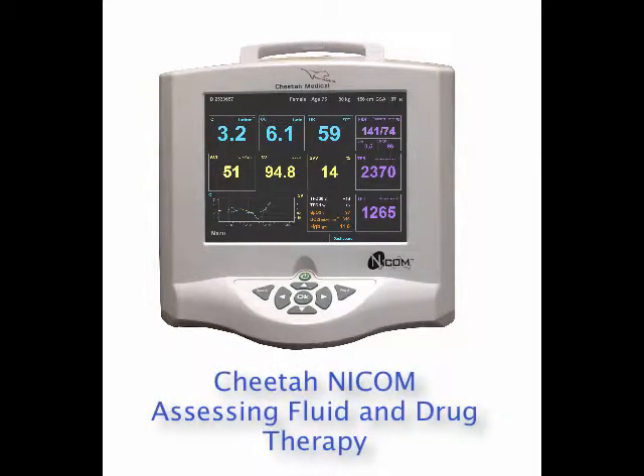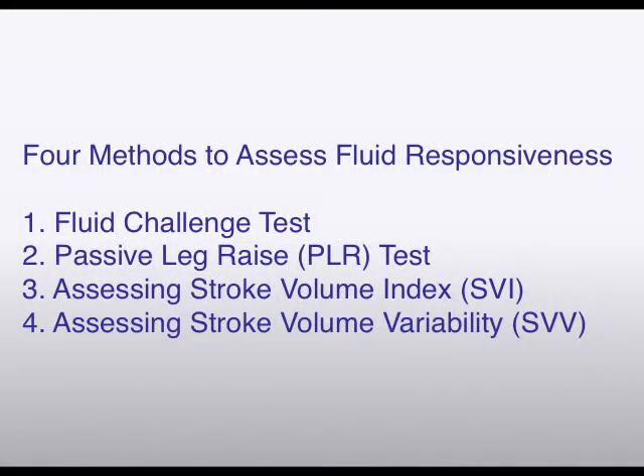There are four methods in which the NICOM monitor can assist the clinician in determining whether a patient is likely to respond to the administration of fluids with an increase in stroke volume, cardiac output, and organ perfusion. The four methods include a fluid challenge test, a passive leg raise test, assessment of the stroke volume index, and assessment of the stroke volume variability.